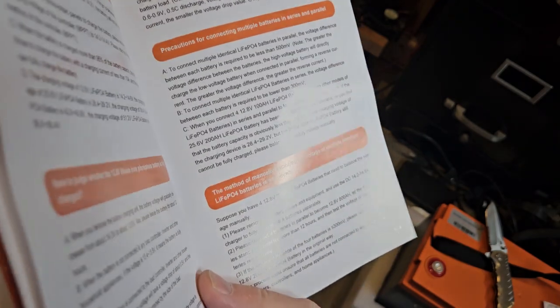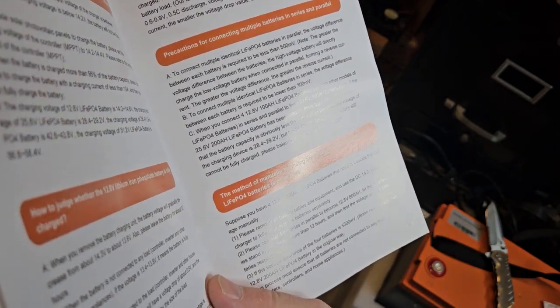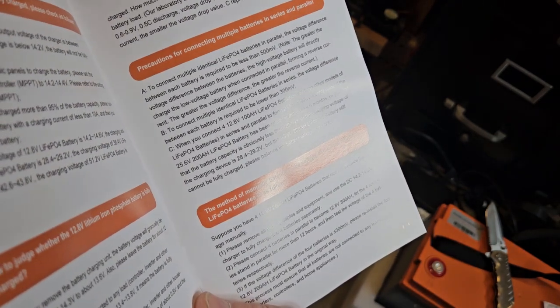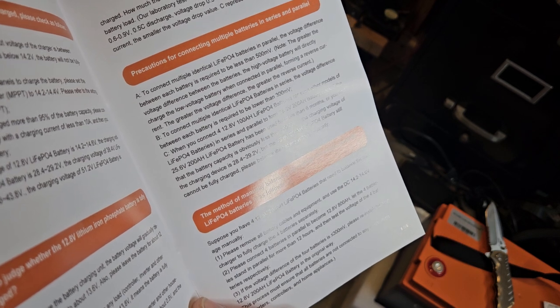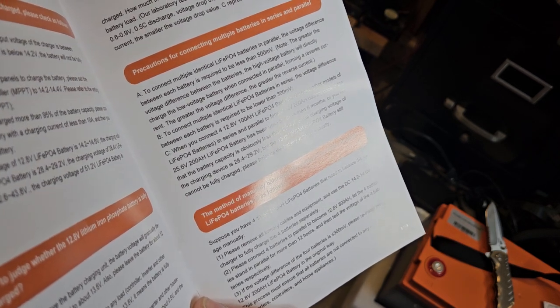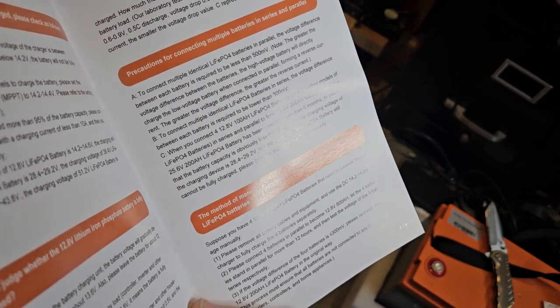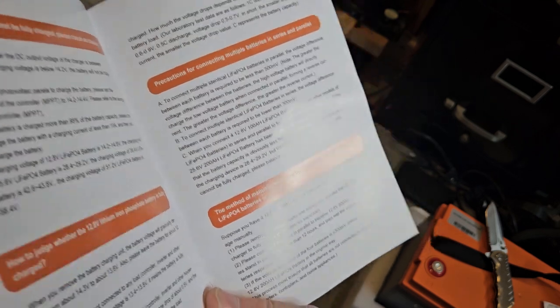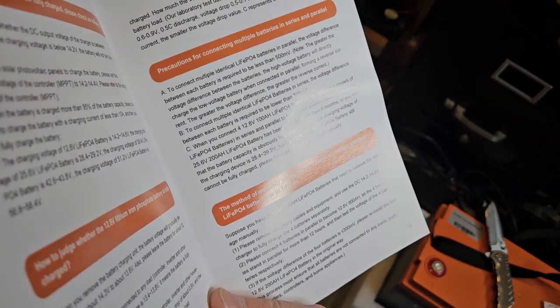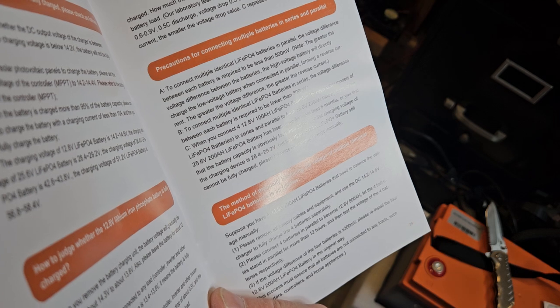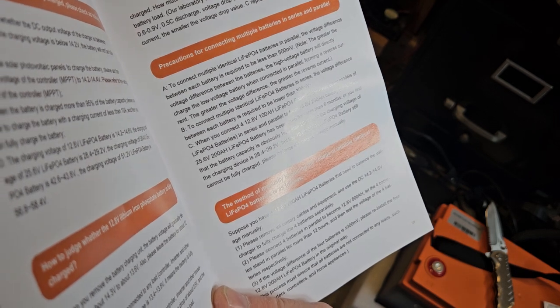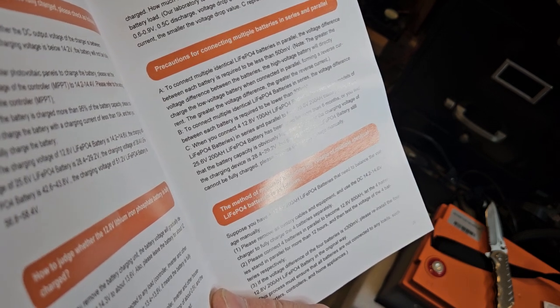Precautions for connecting multiple batteries in series and parallel: to connect multiple identical LiFePO4 batteries in parallel, the voltage difference between each battery should be less than 0.5 volts or 500 millivolts. Note: the greater the voltage difference between batteries, the more the high voltage battery will directly charge the low voltage battery when connected in parallel.